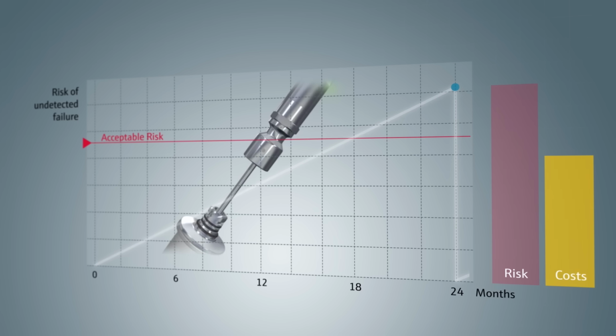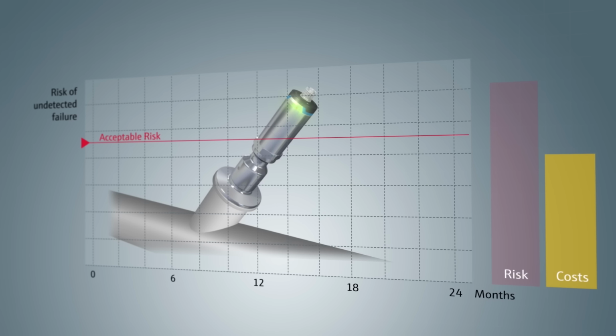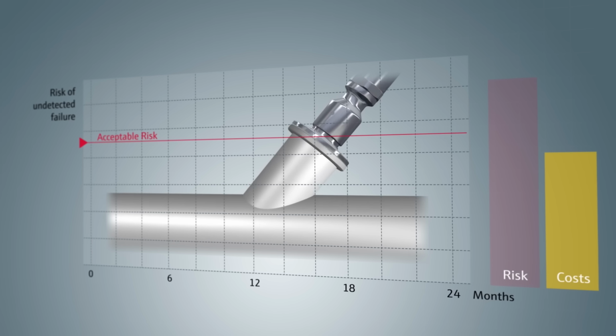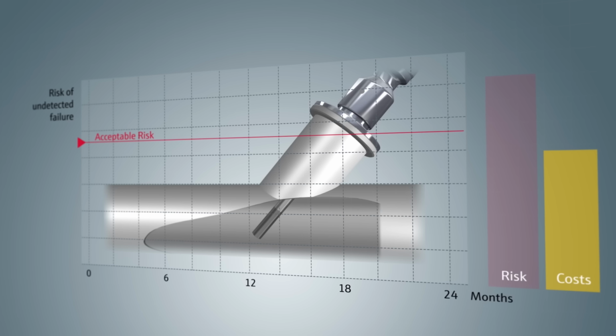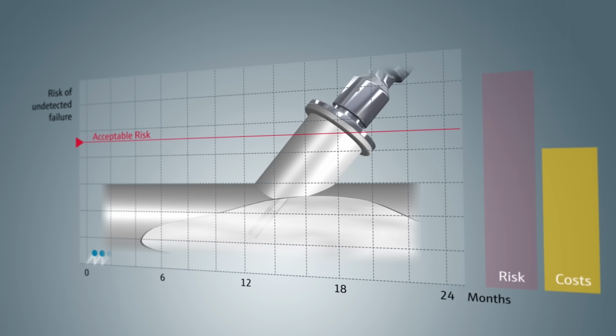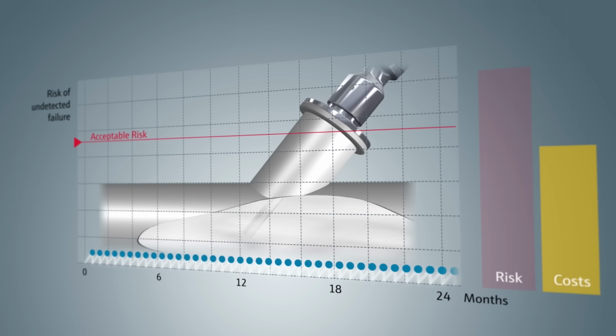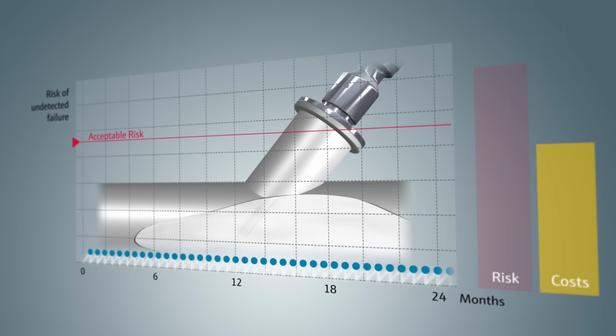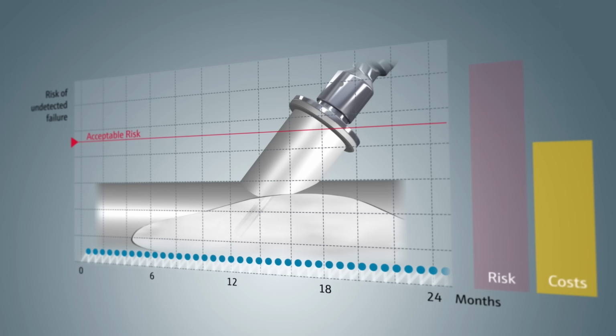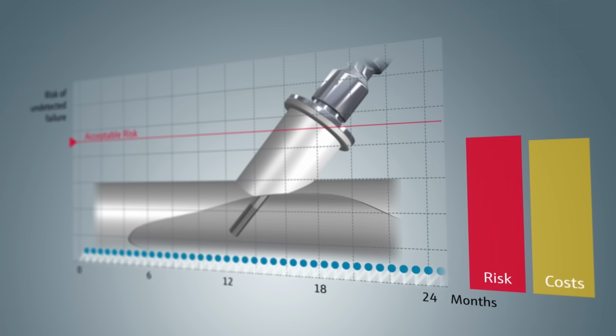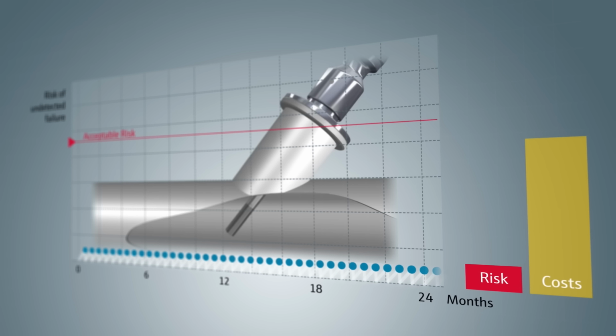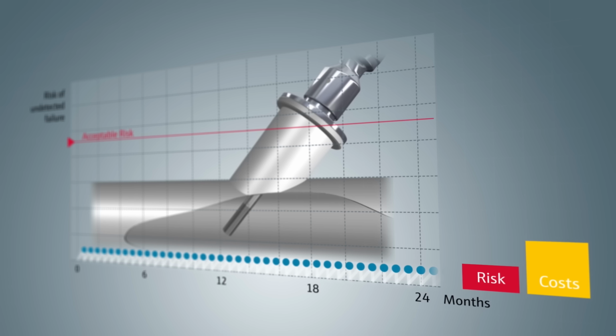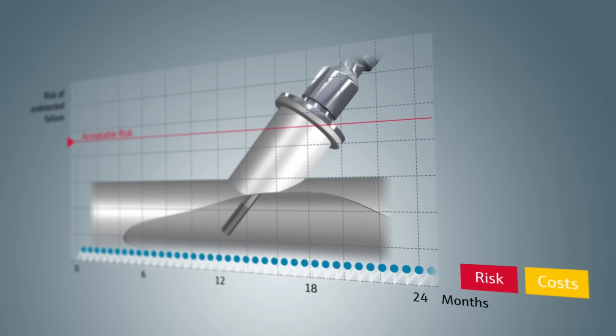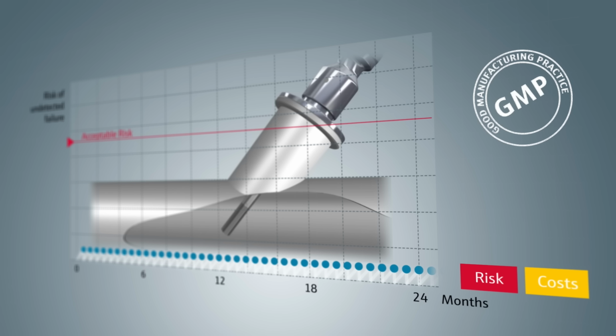Calibration is now carried out automatically in the iTherm TrustSense each time the temperature passes through the Curie point. For example, after each SIP or CIP cycle. These cleaning processes are typically carried out with every batch. This drastically reduces the level of risk, prevents plant shutdowns, and avoids calibration costs. This kind of continuous process verification has even become required by Good Manufacturing Practice, or GMP regulations.